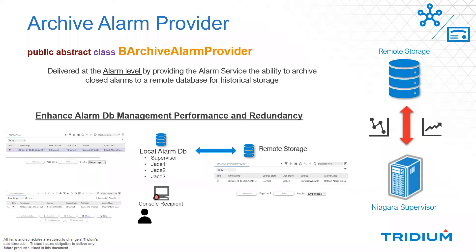What do I mean by that? You would have the console recipient, you acknowledge, you go fix the valve, you come back, you acknowledge that it's all taken care of. That alarm is closed and sits in the database view in the local Niagara alarm station. But now we can set it up to execute at a given interval — maybe 2am — to take the alarms in the Niagara station alarm database and send them to a remote database, since we're no longer really concerned with them but still need to keep them in storage.